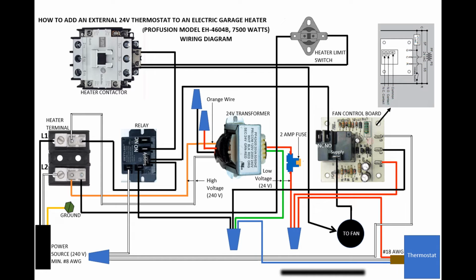Now let's take a look at the transformer and how the wires are connected. This is a 24 volts transformer, since we have 240 volts coming in, and we have 24 volts going down to the thermostat. Now this particular transformer has 3 different high voltages that you can convert to 24 volts. We have 120, 208, and 240 volts.